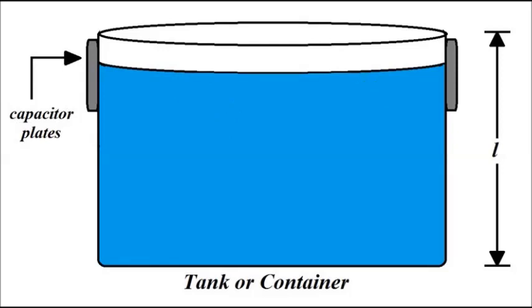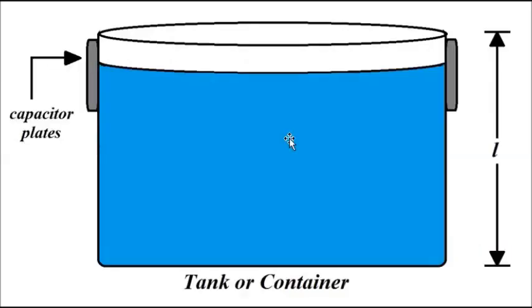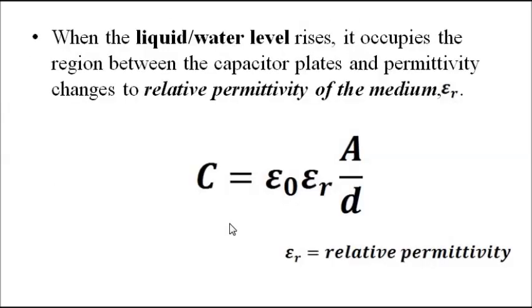When the liquid touches the plates, there will be a change in the relative permittivity. The absolute permittivity — the permittivity of free space or air — remains constant and cannot be changed. But the relative permittivity will change when the liquid level rises and occupies the medium between the two plates, causing a change in capacitance.